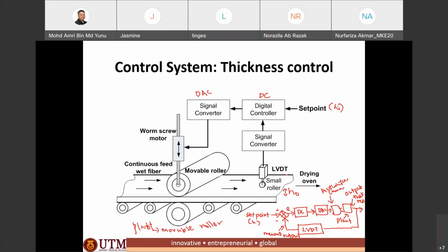So LVDT is just measuring the output, the actual outcome. But the worm screw position will be determined by our set point, not the LVDT. LVDT is a measurement device where it measures the thickness and converts it into measured output, so same unit, same level or same quantity that can be processed by the digital controller.